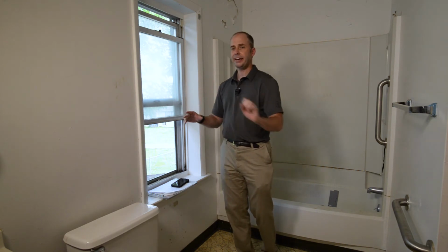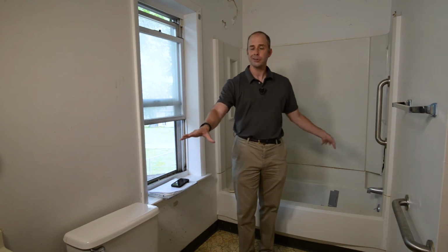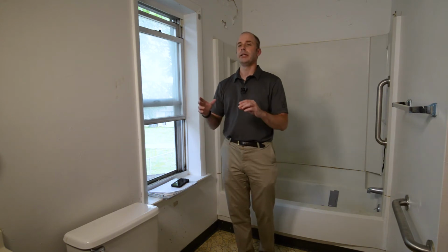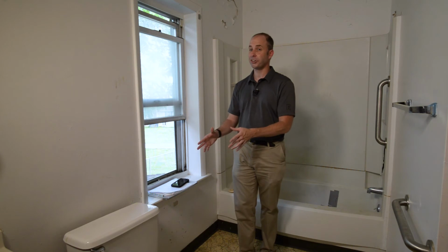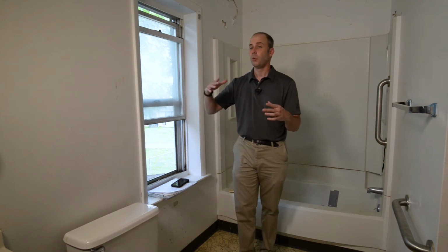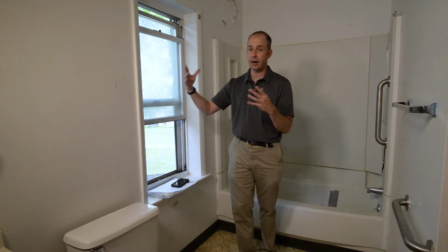With our sink and our tub, you are to have hot and cold water. Not only cold water for a toilet, but hot and cold water for a sink and a tub/shower. Now, with the temperature of those, it's to be a minimum of 110 degrees Fahrenheit and a maximum of 140 degrees Fahrenheit. Why is the maximum 140? Because over that point, scalding could be created by higher temperatures. So it's to be no more than that.